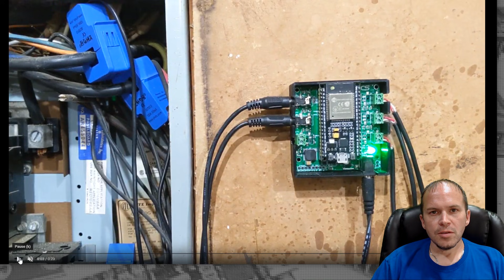Other than that, the CT clamp installation is fairly simple. They just get clipped over the wire, so no wiring has to be removed — it's non-invasive and doesn't cut into the wire itself. You can see here I have mine installed on the side of the panel, in a little 3D printed case next to the panel itself, and it works great.